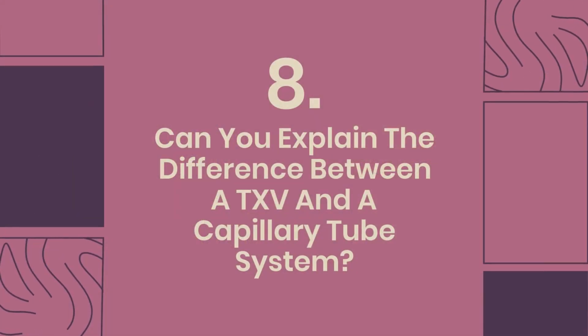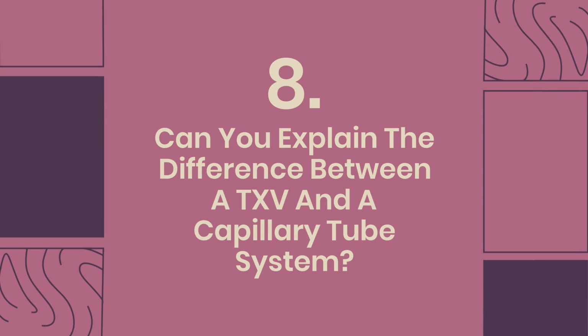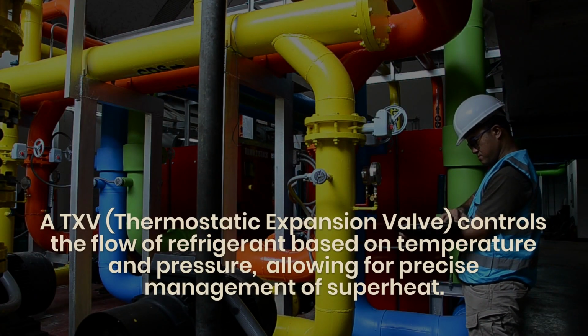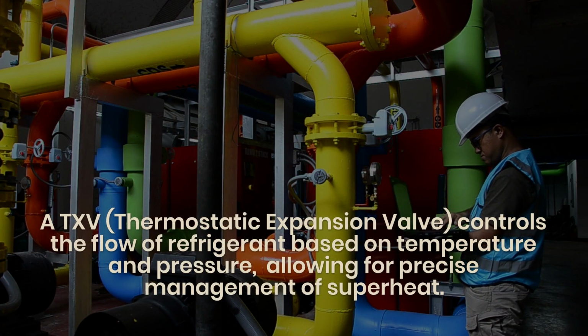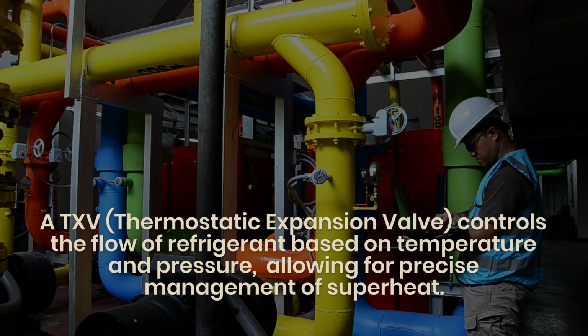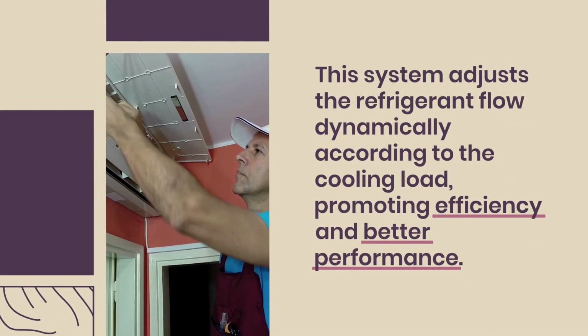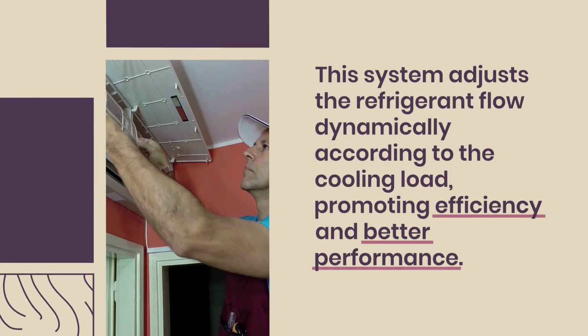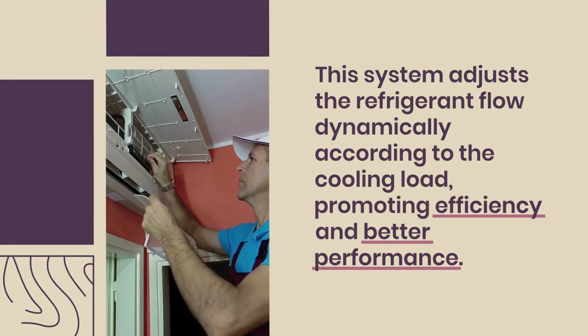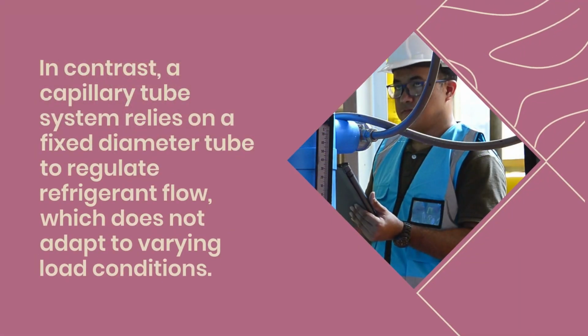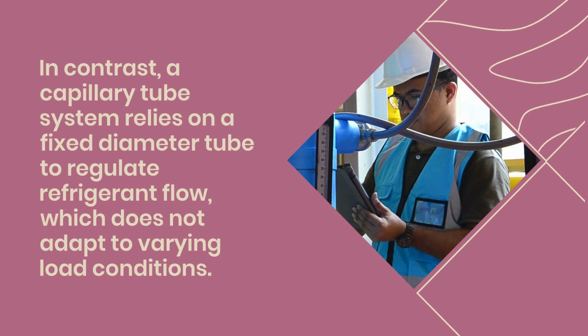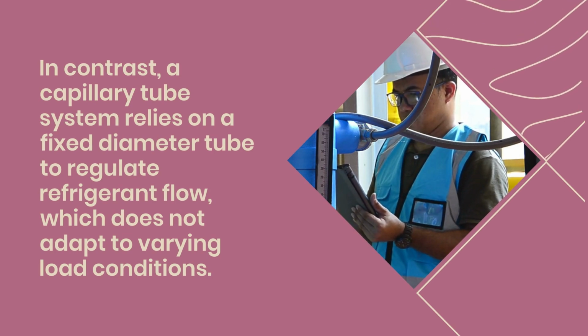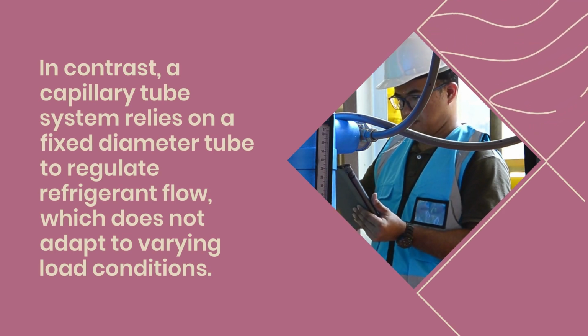8. Can you explain the difference between a TXV and a capillary tube system? A TXV, thermostatic expansion valve, controls the flow of refrigerant based on temperature and pressure, allowing for precise management of superheat. This system adjusts the refrigerant flow dynamically according to the cooling load, promoting efficiency and better performance. In contrast, a capillary tube system relies on a fixed diameter tube to regulate refrigerant flow, which does not adapt to varying load conditions.